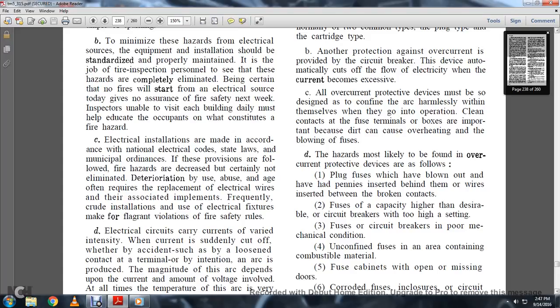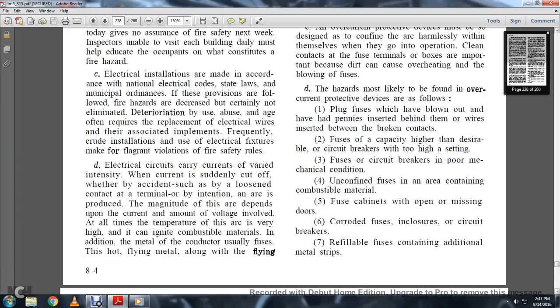Cleanliness and contact with the fuse terminals and boxes is important because dirt can cause overheating and the blowing of the fuse. The hazard most likely to be found with overcurrent protective devices is fouling: plug fuses blown out and pennies inserted behind them, or wires inserted between the broken contacts.